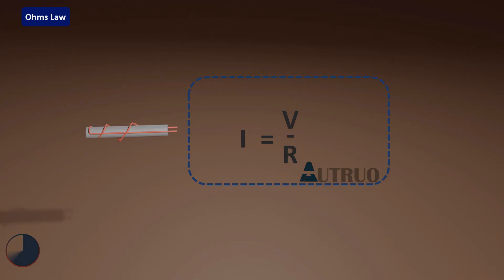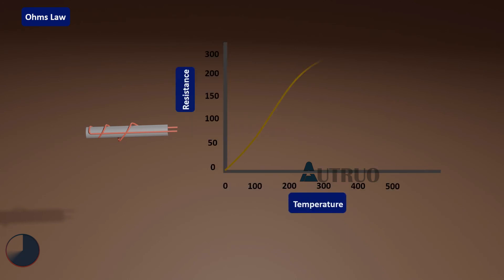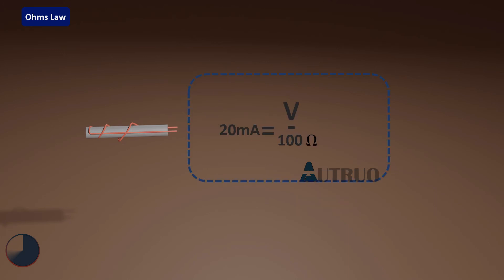As we all know, voltage is a result of current and resistance combination. When current is held constant and the temperature changes, the resistance of the material also changes accordingly. Then the voltage can be measured. This measured voltage can be used to determine the temperature applied to the PT100.